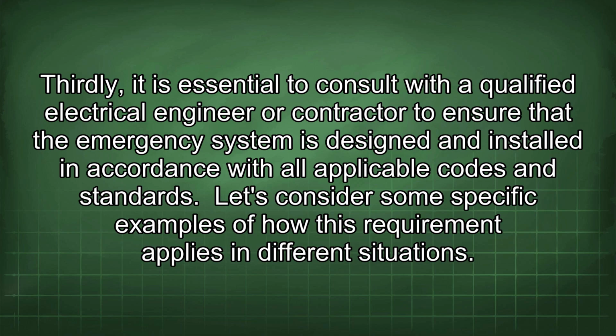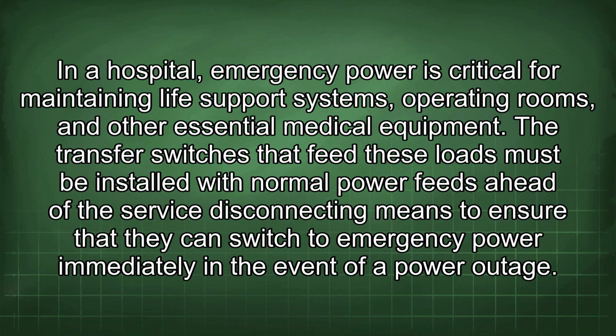Let's consider some specific examples of how this requirement applies in different situations. In a hospital, emergency power is critical for maintaining life support systems, operating rooms, and other essential medical equipment. The transfer switches that feed these loads must be installed with normal power feeds ahead of the service disconnecting means to ensure that they can switch to emergency power immediately in the event of a power outage.